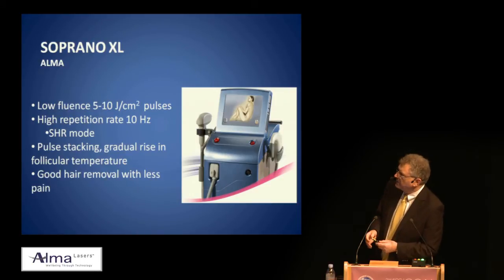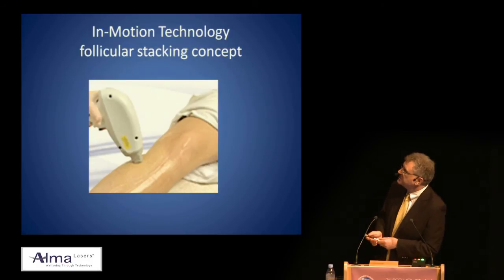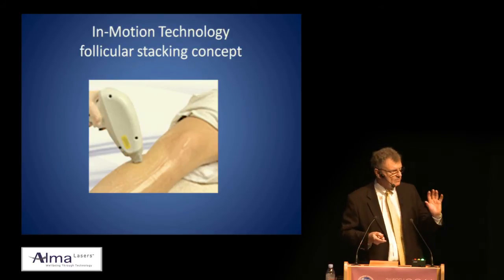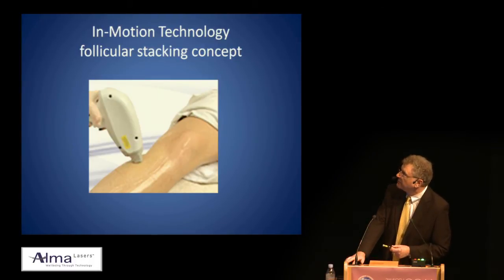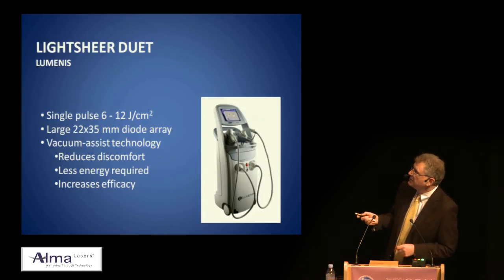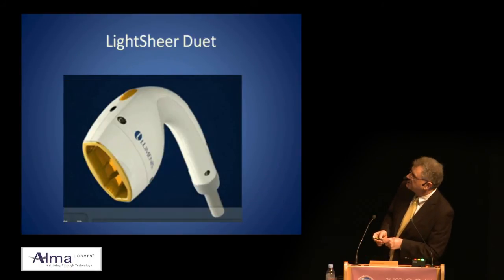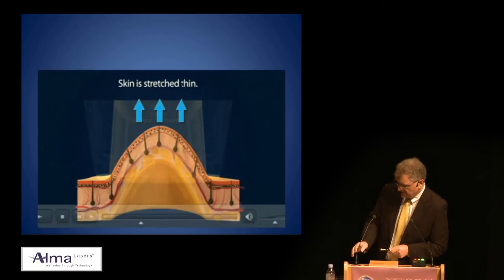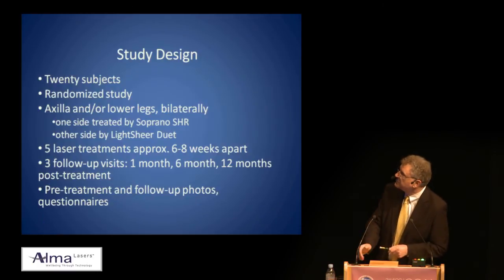The Soprano 810 claims good hair removal with less pain. It operates in motion — you never keep it in one place, constantly moving and pulsing repeatedly. Versus the LightShear Duet: single pulse, 6 to 12 joules depending on tolerance, a large 22 by 35mm diode array with vacuum assisted technology, which reduces discomfort. Less energy is required compared to the traditional LightSheer device, and it increases efficiency. The suction unit draws the skin up toward the diodes, then you position it and flash after the skin is very close to the diodes.